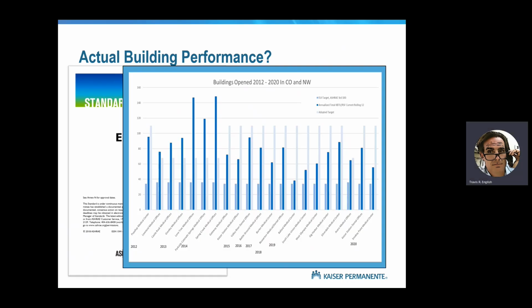So these are the buildings that we own in those regions, right? These are not the legacy buildings. These are the buildings that have been opened in the last decade. So the boilers, chillers, rooftop units, controls, all less than 10 years old in these buildings. In Washington, we're actually in pretty good shape because they adopted that higher target, right? They adopted 100 EUI. If they were to adopt ASHRAE 100, which is the little blue line at 30 EUI down there, we would be in a world of hurt.